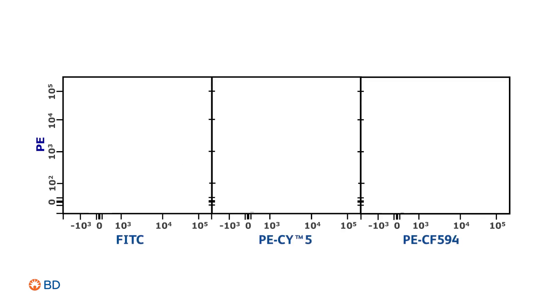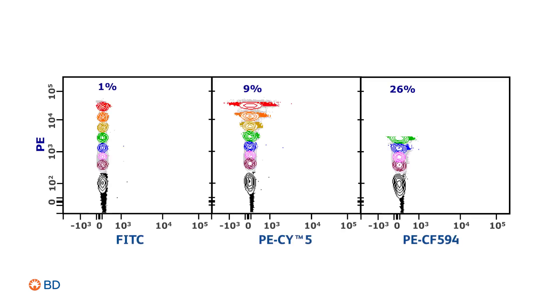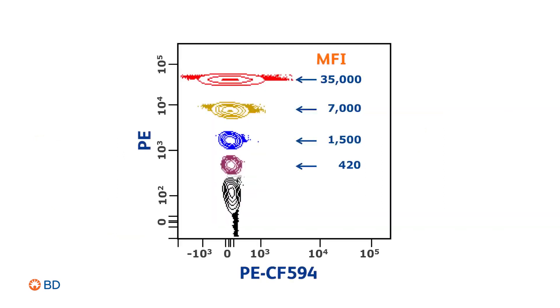The larger the fluorescence spillover, shown here from 1% to 26%, the greater the spread. Similarly, at any given PMT voltage, the antigen density and the fluorochrome brightness together determine the reagent brightness, measured as median fluorescence intensity, or MFI. As you can see, the higher the MFI, the greater the spread.